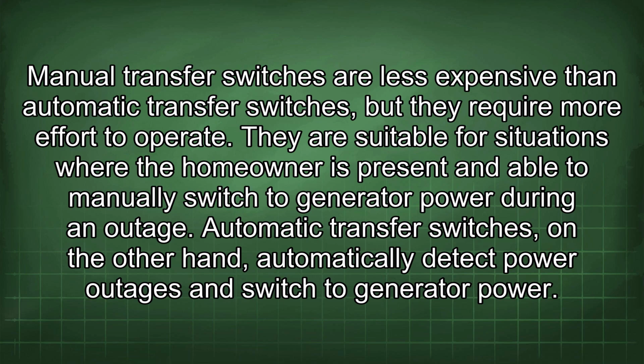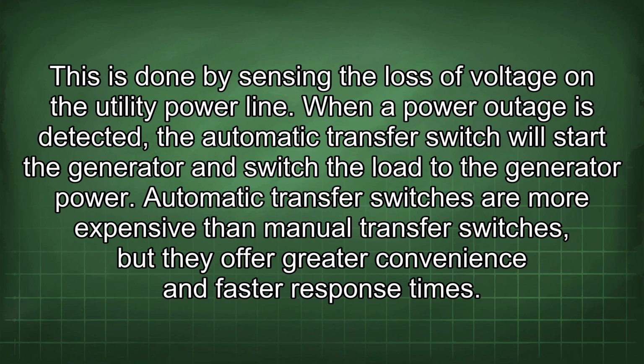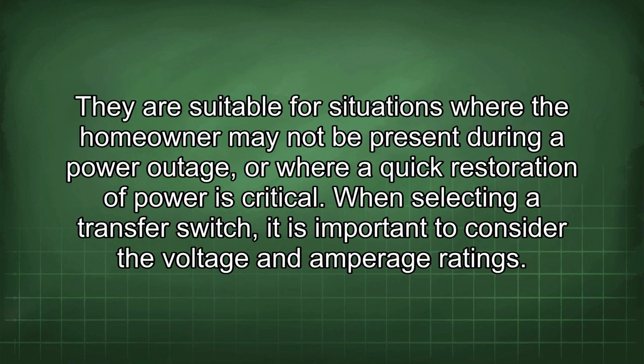Automatic transfer switches, on the other hand, automatically detect power outages and switch to generator power. This is done by sensing the loss of voltage on the utility power line. When a power outage is detected, the automatic transfer switch will start the generator and switch the load to the generator power. Automatic transfer switches are more expensive than manual transfer switches, but they offer greater convenience and faster response times. They are suitable for situations where the homeowner may not be present during a power outage, or where a quick restoration of power is critical. When selecting a transfer switch, it is important to consider the voltage and amperage ratings.